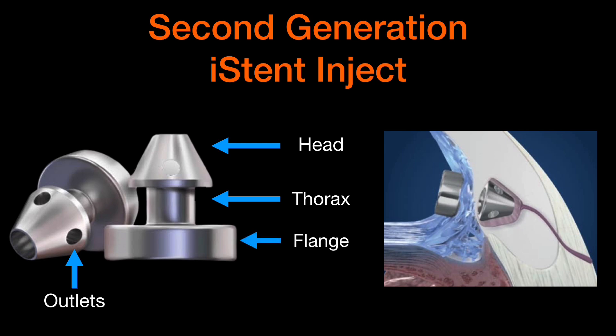It is made of surgical grade non-ferromagnetic heparin-coated titanium. The second generation iStent inject G2 has three parts: a head with central and side flow outlets which sits in the Schlemm's Canal, the thorax which traverses the trabecular meshwork, and a wide flange which rests in the anterior chamber.